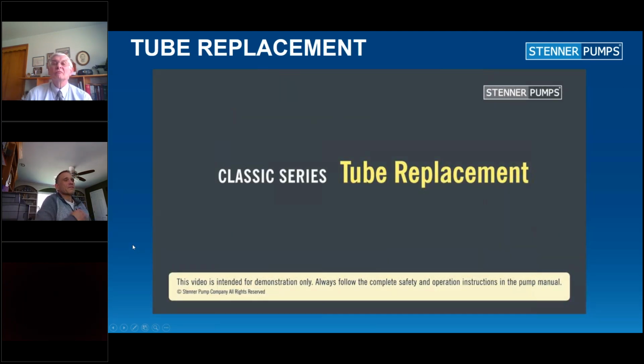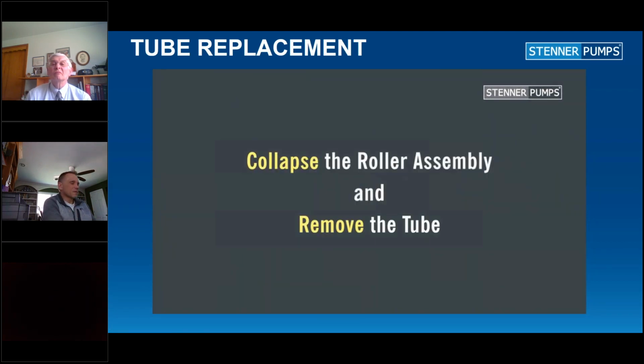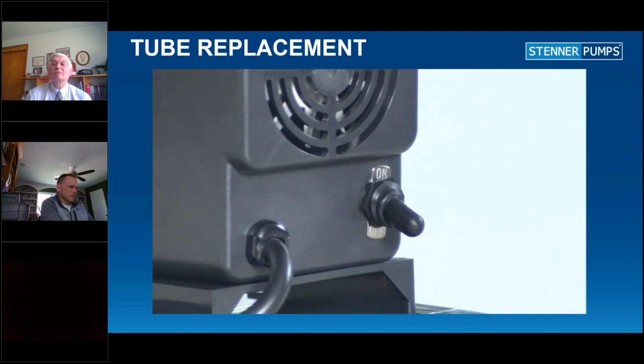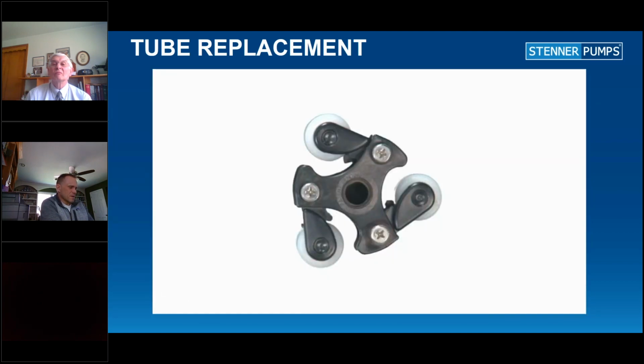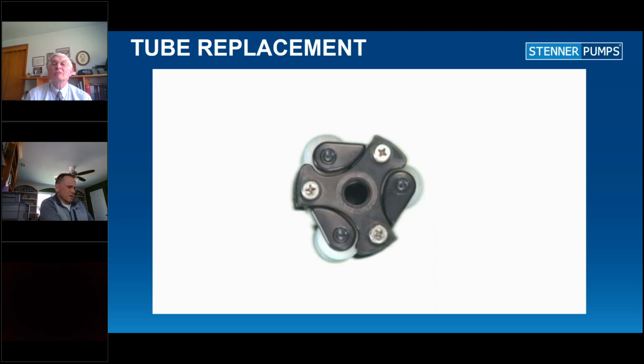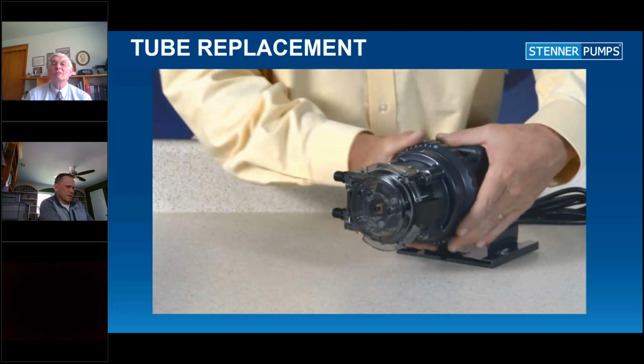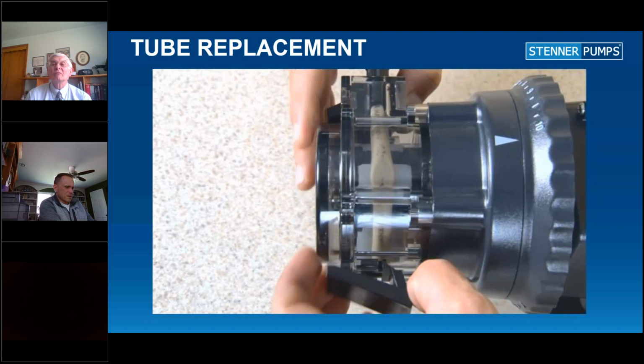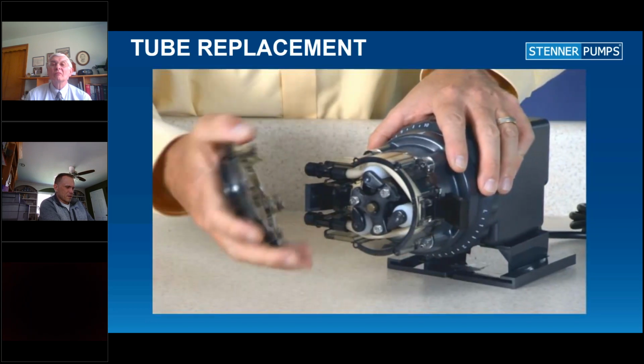Hey everyone, Mitch here, and we are going to replace the tube on our Stenner Classic pump. First, we need to collapse the roller assembly and remove the tube. Make sure the pump is off and the cord is unplugged. To remove the tube, the roller assembly needs to be collapsed. First, set the feed rate control to 10. Then, unlatch the latches and remove the tube housing cover.